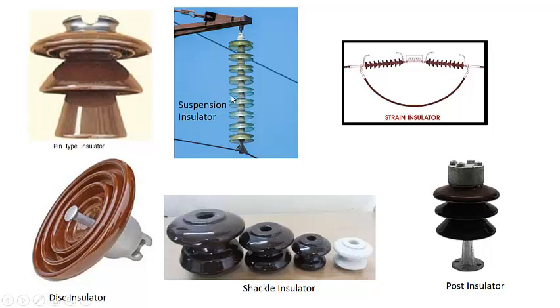This is the suspension type insulator. You can see 1 2 3 4 5 6 7 8 9, these are made of glass. These are the 9 disc insulators connected in series, and they are suspended from the cross arm to the conductor, and here there will be no tension in the transmission line.